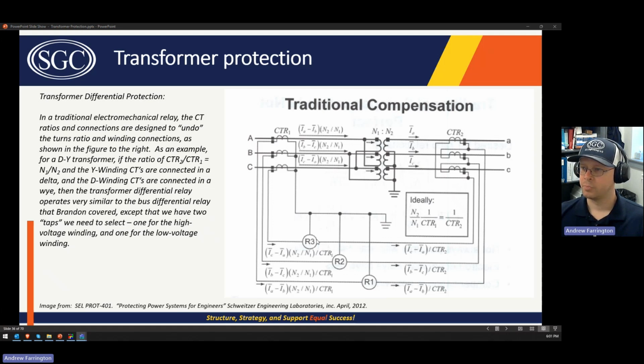So we're going to start with an electromechanical relay. What you want to do is have your CTs, the CT ratios, essentially undo the differences of the transformer. What do I mean by that? Well, if you have a turns ratio of N1 to N2, say this is 10 to 1, ideally you'd have the CTs have a ratio where this is 10 times higher than this ratio. Especially for a YY transformer, that math is easy because basically if you have 1 amp in, you get 10 amps out, and so you can adjust those CT ratios such that the current that actually flows to the relay is equal. So that's great.